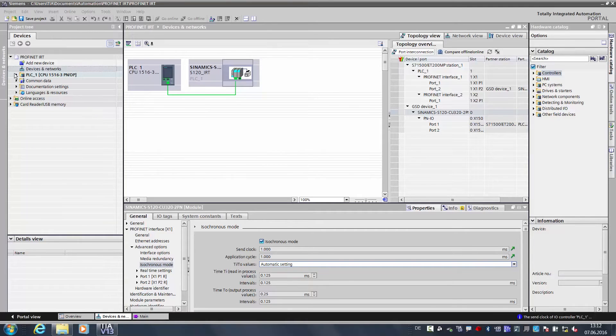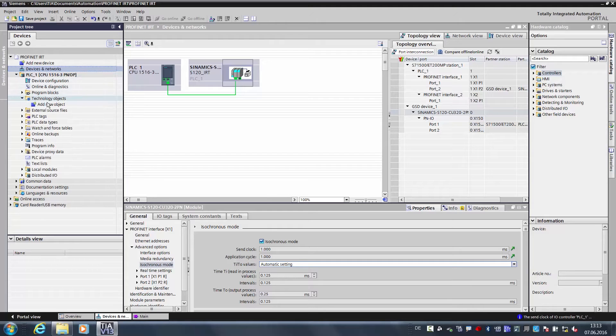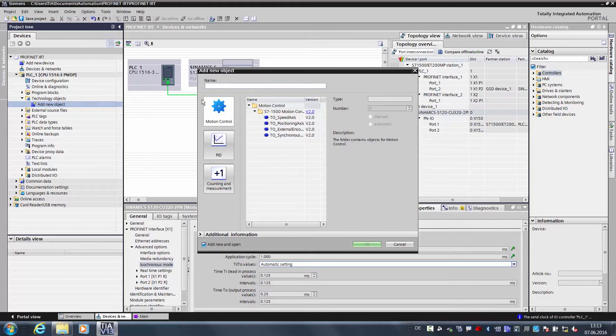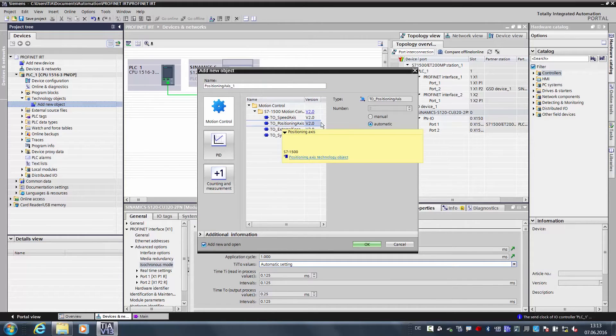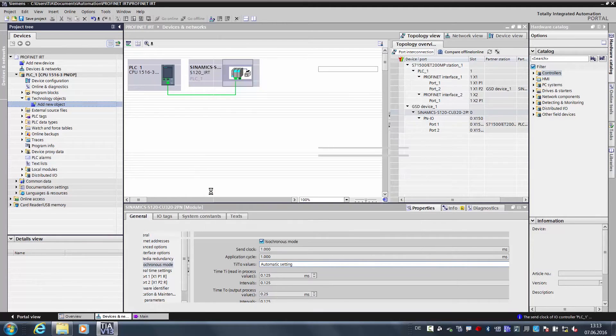Now we are finished with the hardware configuration, and together we want to create a motion control program. For this we want to first create two technology objects in the S7-1500. We open the controller, go to Technology Objects, and Add New Technology Object. Now we select a motion control technology object, and here first of all the positioning axis. The positioning axis is intended to later be the control axis in our synchronized motion control system.